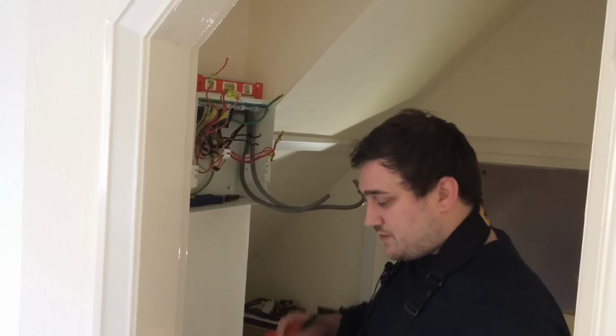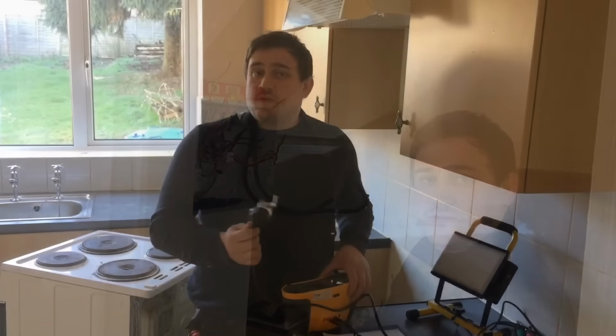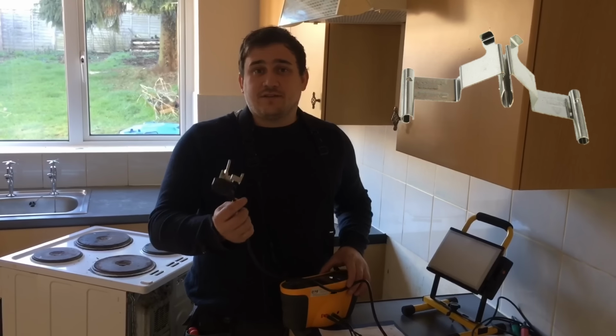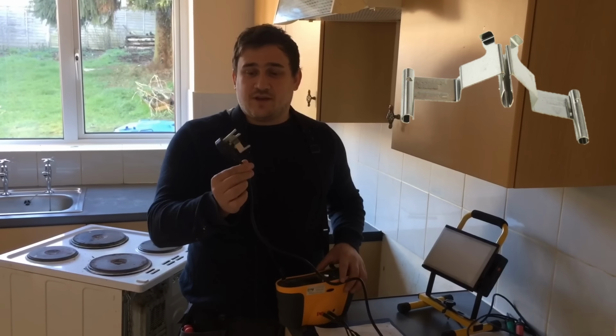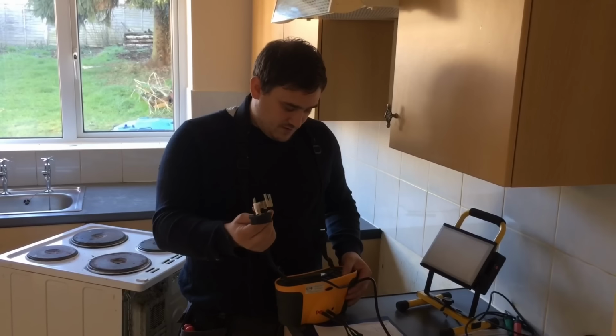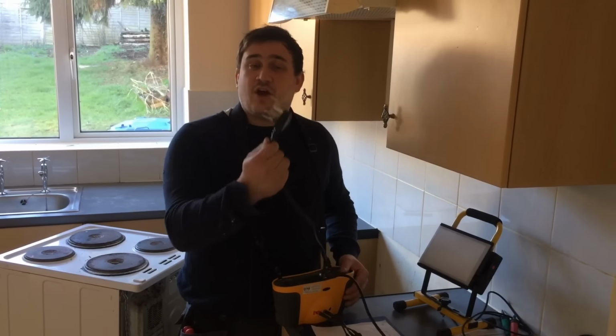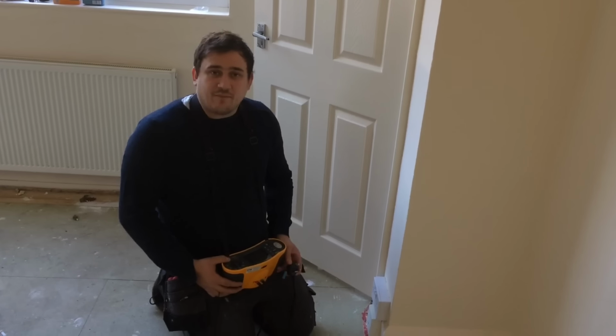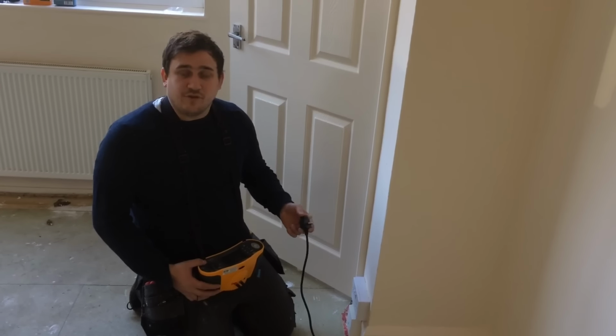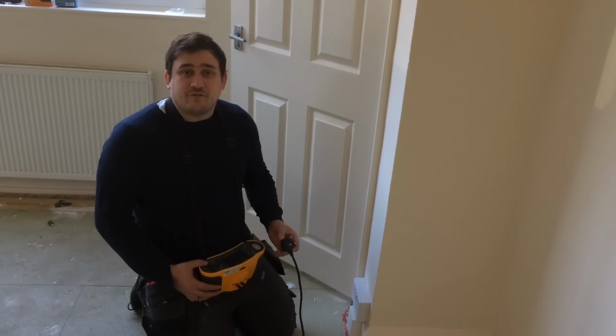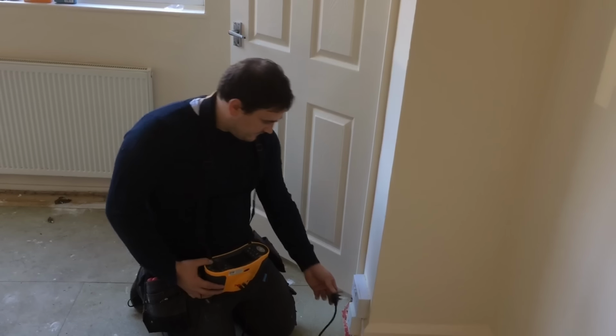Now I'm going to put in my plug-in tester and go around the sockets. Before I go around to my sockets and test for my values, I've changed my lead to a plug-in lead test, so I've just got to zero that. So I've zeroed that between the line and the CPC connections on the plug. Now I've zeroed my leads, I'm going to go around my socket outlets, and now I can fully confirm polarity and confirmation that it is a ring final circuit.